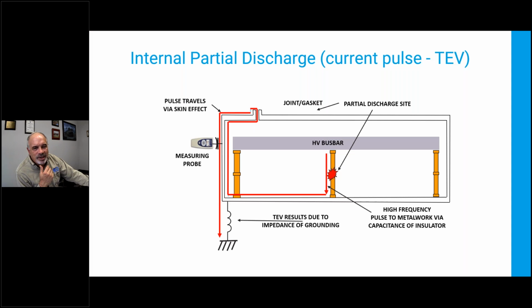TEV, now TEV is a bit odd. It's probably the least believable thing I'll talk about today, but TEV is a voltage that appears on the outside of the switchgear as a result of discharge inside the switchgear. So in this picture, I've got a piece of bus cabinet, and I've got a bus bar sitting on insulators, and I've got a defect in my insulator. I've got that void. So I get a discharge, I get this current pulse that goes down the insulator, and it hits the inside of the cabinet.